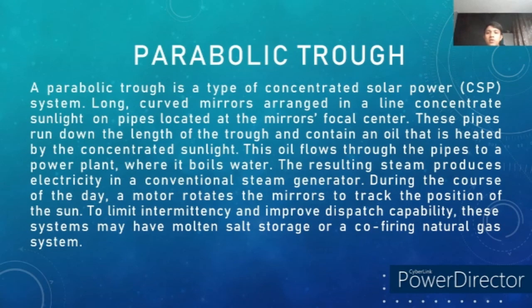This oil flows through the pipes to a power plant where it boils water. The resulting steam produces electricity in a conventional steam generator. During the course of the day, a motor rotates the mirrors to track the position of the sun. To limit intermittency and improve dispatch capability, this system may have molten salt storage or a co-firing natural gas system.